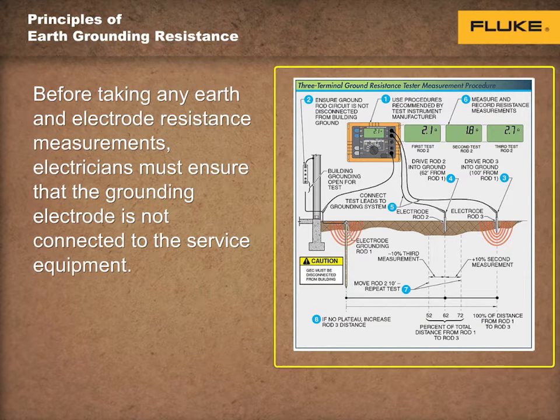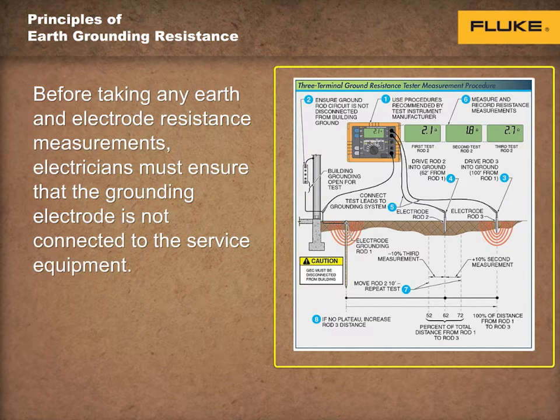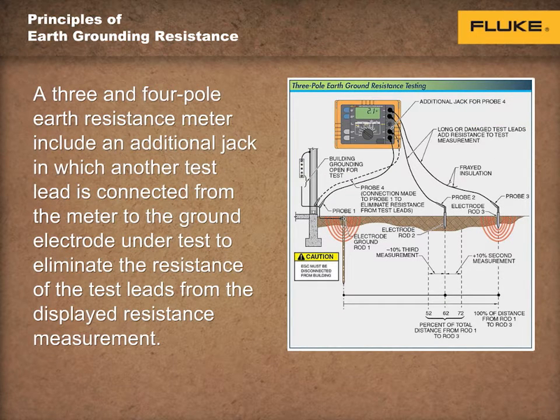A 3-pole ground resistance meter is a common meter used to test grounding systems. This method is very reliable, accurate, and can be used on any size grounding system, as shown on the screen. 4-pole test measurements are suitable for most applications for measuring the resistance of a grounding system in order to meet the minimum resistance requirement listed by codes, typically 25 ohms for a rod, pipe, and plate electrodes, provided the test instrument leads and connections are acceptable.